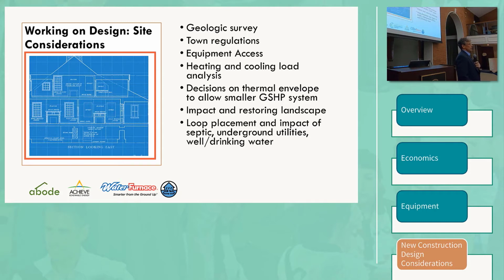So there has to be commitment at the time of the design that this is what the insulation package is going to be, because we typically go in and do our drilling very early in the project, and you can end up with a ground heat exchanger that's too small because they made the house a little bit more crappy than they led you to believe. So design professionals, architects should try to keep that in mind. And if there's been a commitment to a particular insulation and window and door package, stick to it and cut corners someplace else, or don't have us start work until everything's really finally decided.